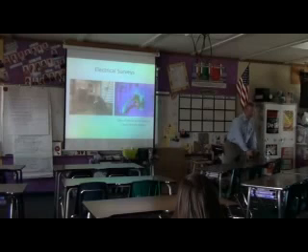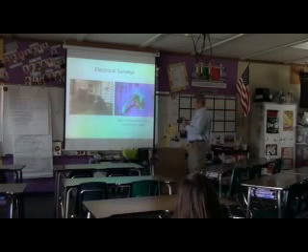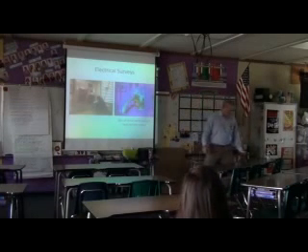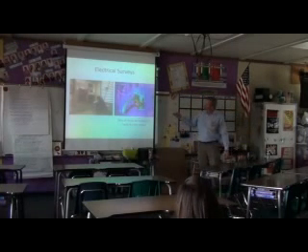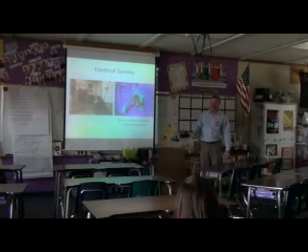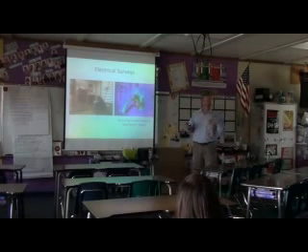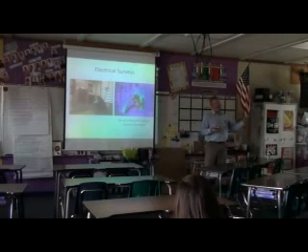I just simply turn on a camera. Yep, this one doesn't look good. And then I calculate it and tell them how big of a risk it is. Do you guys know this is 150 degrees and this other wire is 65? This is considered a critical fault. And do you know that because I know the fault levels and because I was trained on it and because I knew how to take a picture of it, I save them potentially millions of dollars.